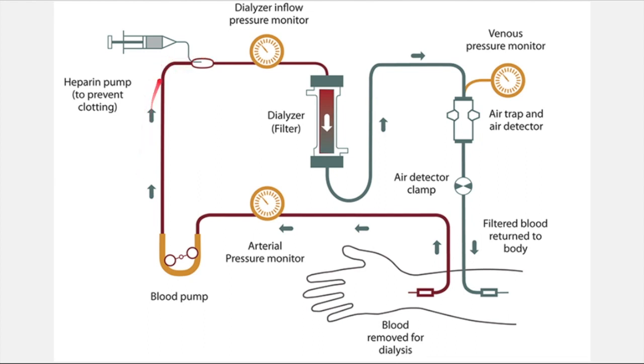And along this line, there's also the saline solution that is going to be used after the procedure to flush out the line, which then goes through here into the dialyzer or the artificial kidney, which then filters out all the toxic wastes, the urea, and other small particles.